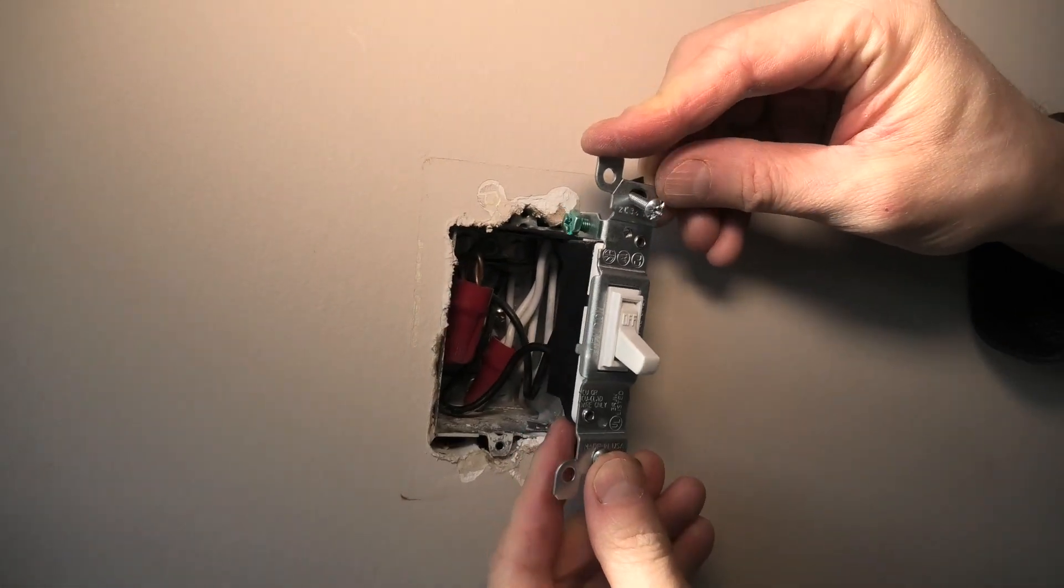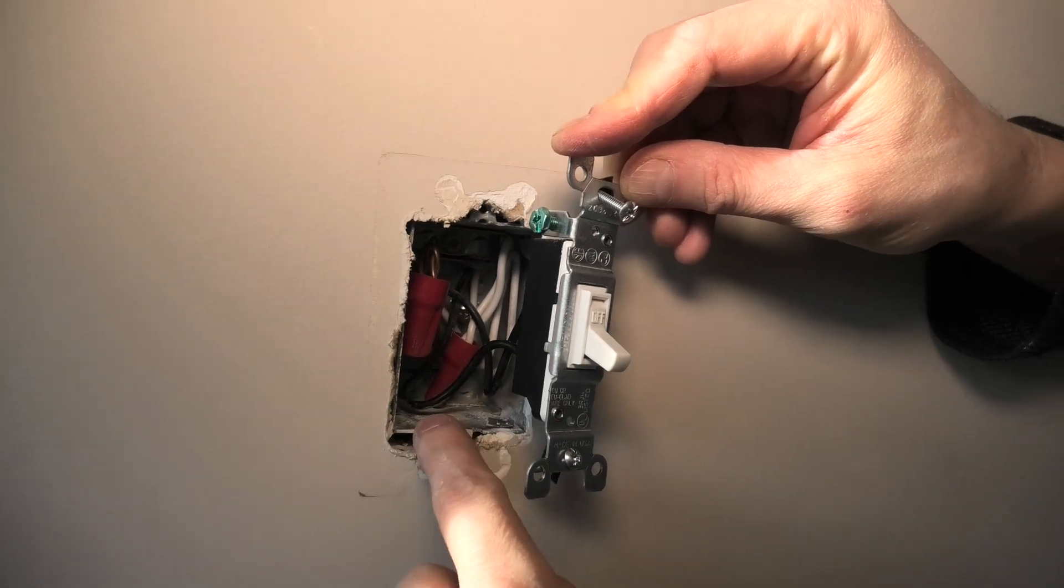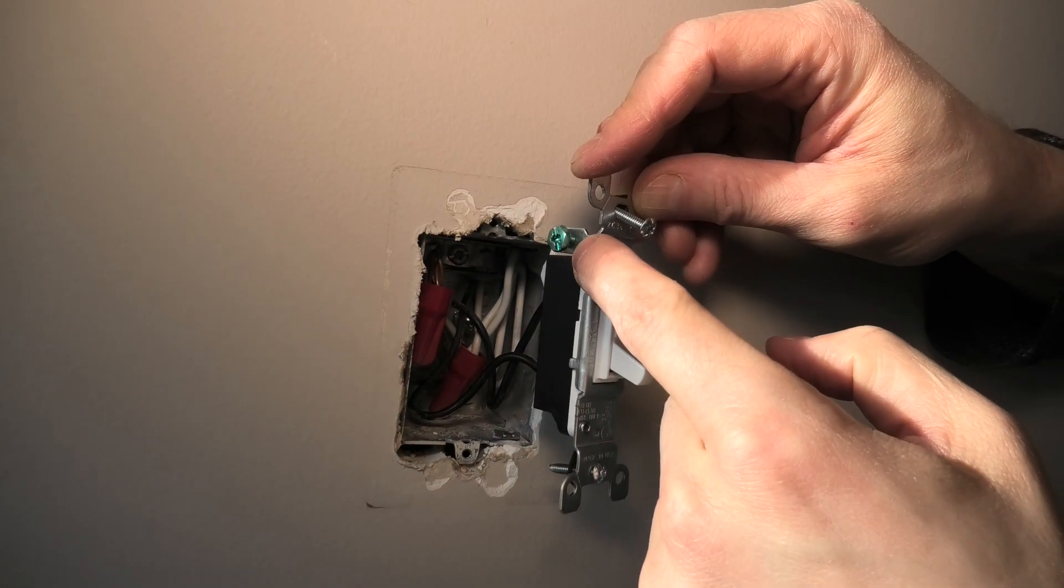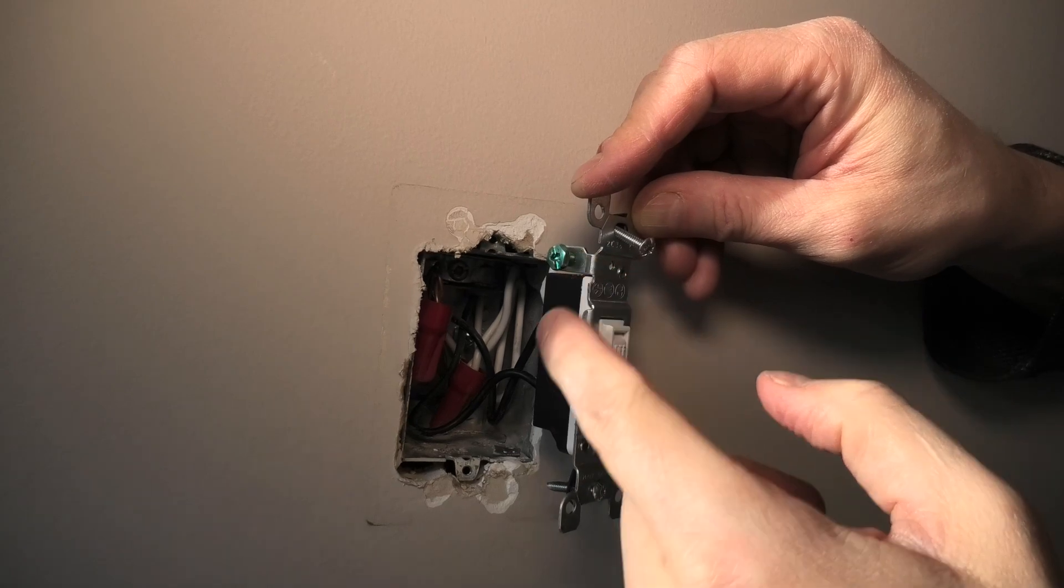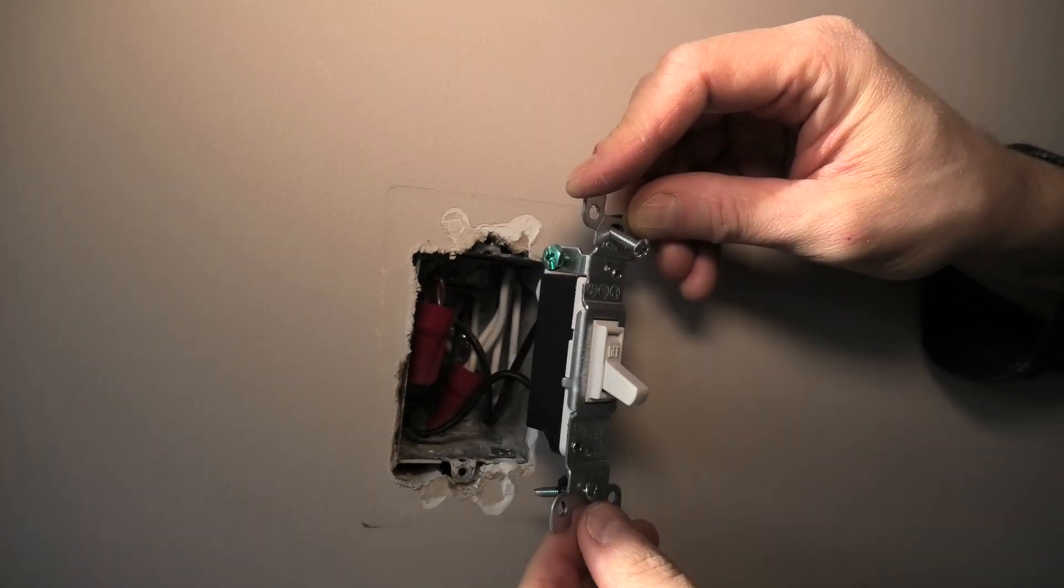And in general, if you are not certain if your box is grounded, you need to connect this grounding screw to the grounding wires inside the box.